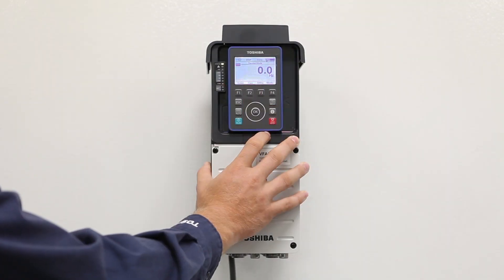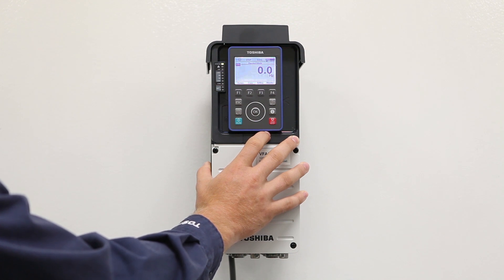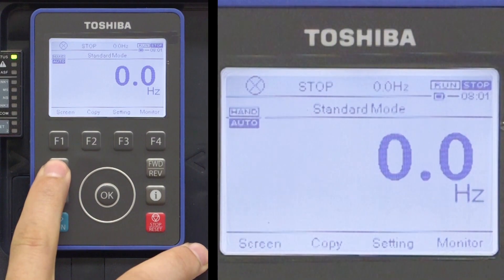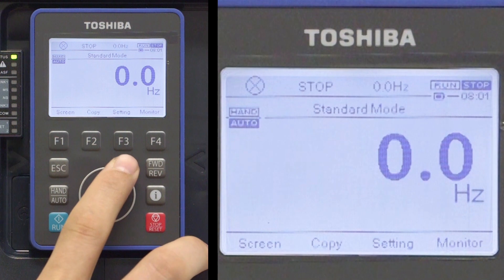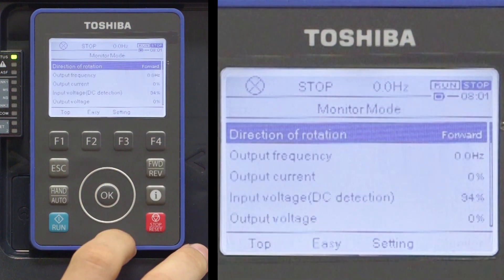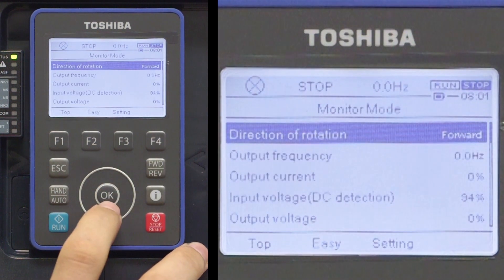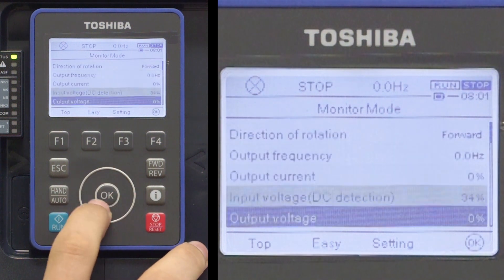The AS3 adjustable speed drive is able to retain the past trip history along with detailed timestamped information about the drive status at the time of the trip. To access the trip history, press the Escape key twice or the F4 key to display the monitor mode. From this screen, scroll clockwise to go down until past trip 1 is displayed.